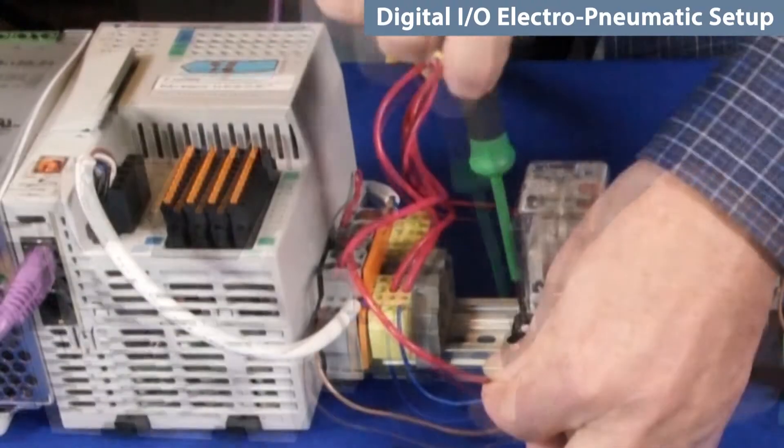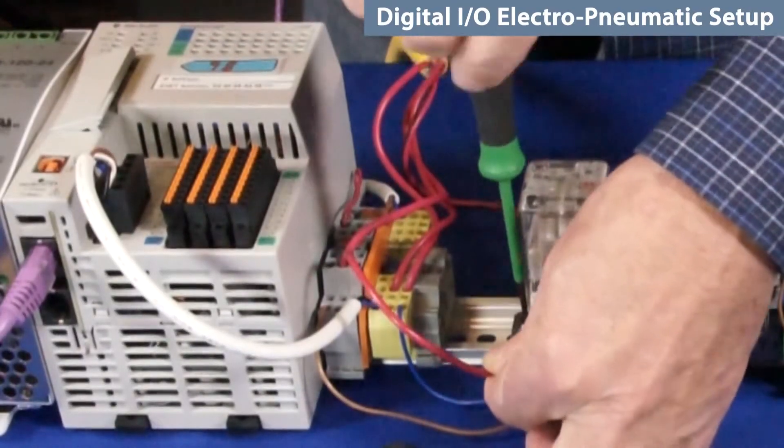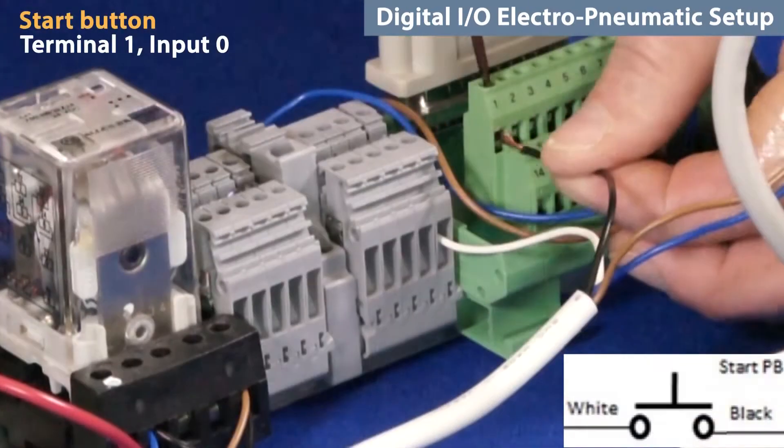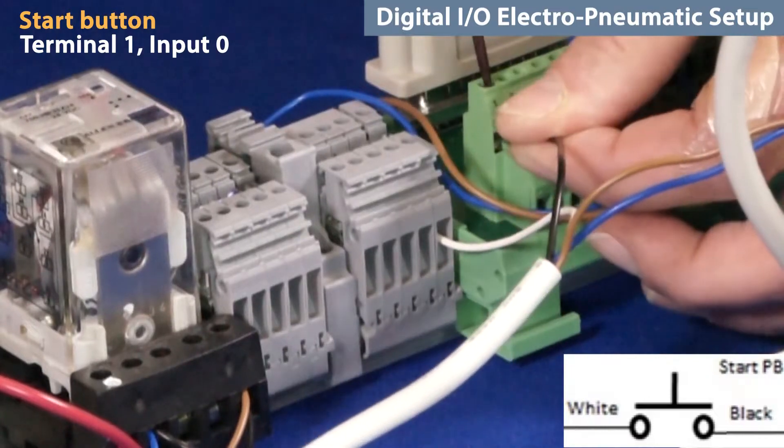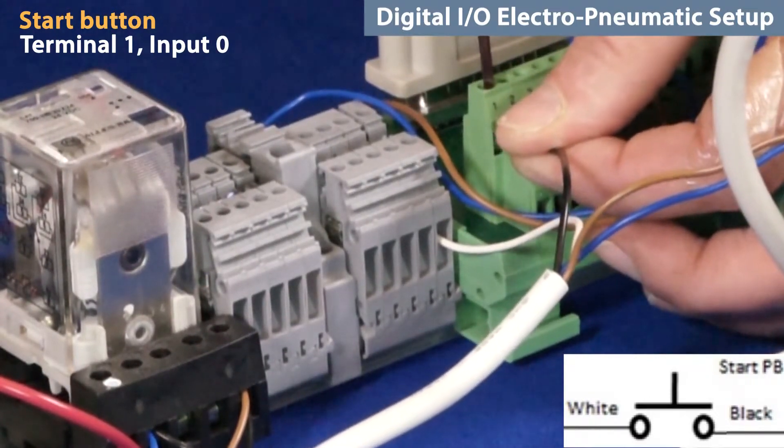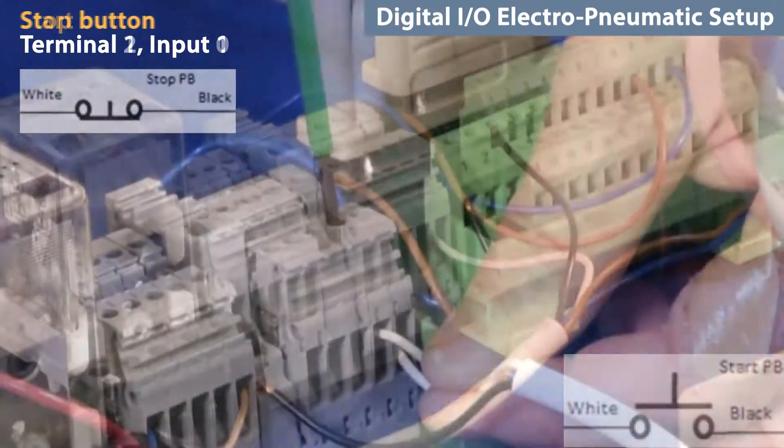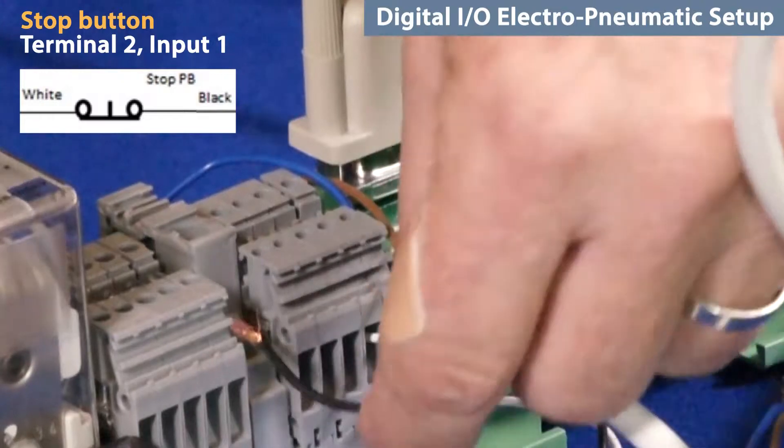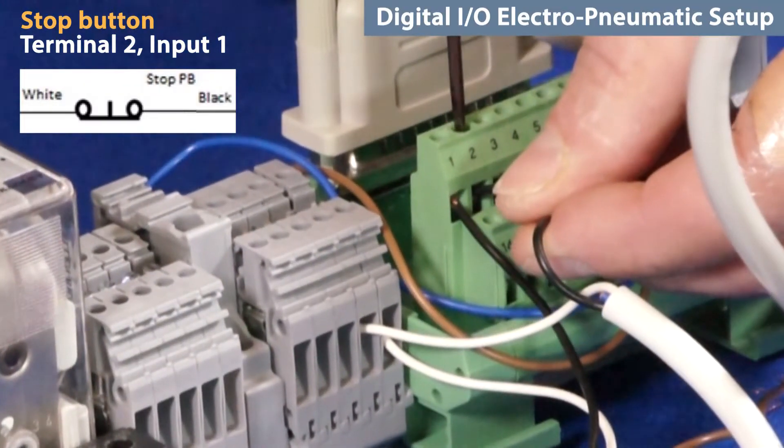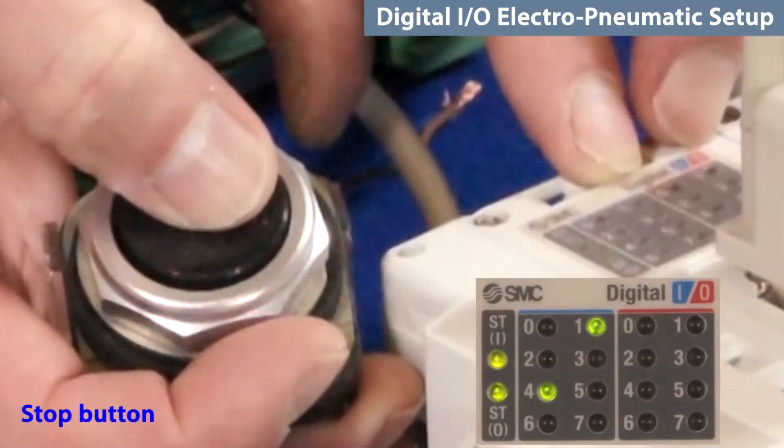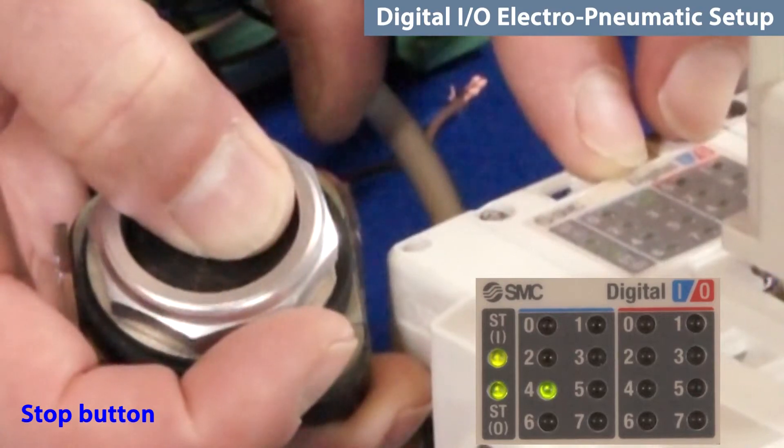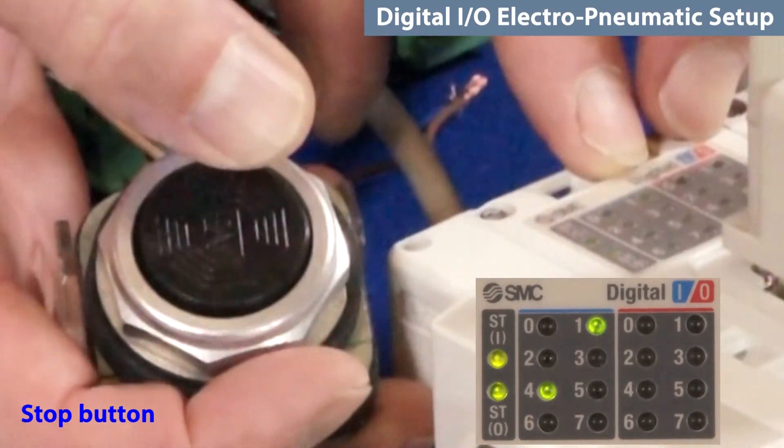Reroute the 24-volt DC power through the E-stop relay. Wire the normally open start button to terminal 1, which is input 0, and the normally closed stop button to terminal 2, which is input 1. Verify by checking the LEDs on the DMPE module.